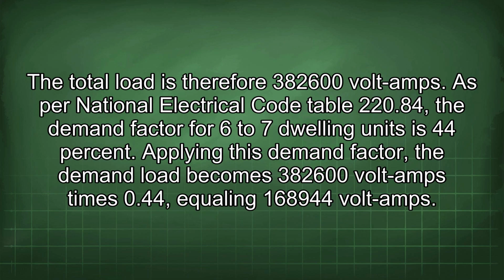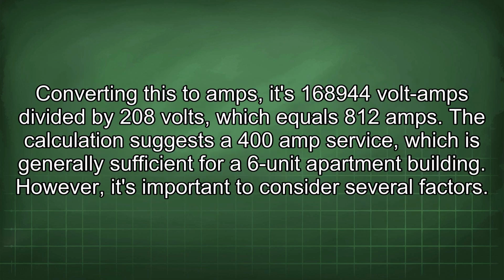The total load is therefore 382,600 volt amps. As per National Electrical Code Table 220.84, the demand factor for 6 to 7 dwelling units is 44%. Applying this demand factor, the demand load becomes 382,600 volt amps times 0.44, equaling 168,944 volt amps. Converting this to amps, it's 168,944 volt amps divided by 208 volts, which equals 812 amps.